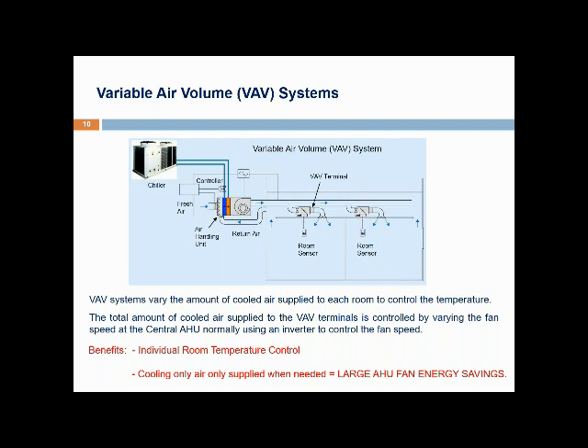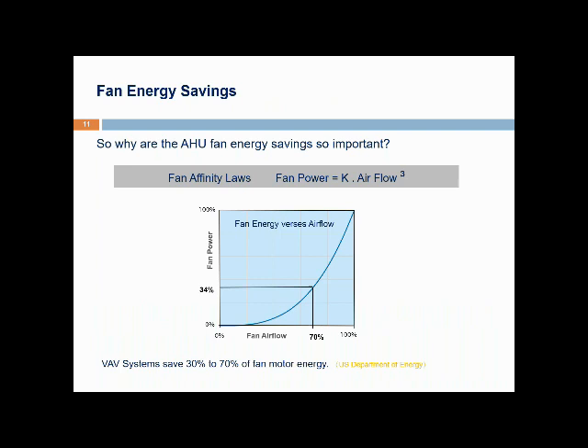VAV systems vary the amount of cool air supplied to each room to control the temperature, and the total amount of cooled air supplied to the VAV terminals is controlled by varying the fan speed of the central air handling unit, normally using an inverter. This provides individual room temperature control and reduces the amount of air circulated around the building when not needed, resulting in large AHU fan energy savings. The fan power is proportional to the cube of the airflow — so even a small reduction down to 70% airflow results in a large reduction in fan power down to 34%.